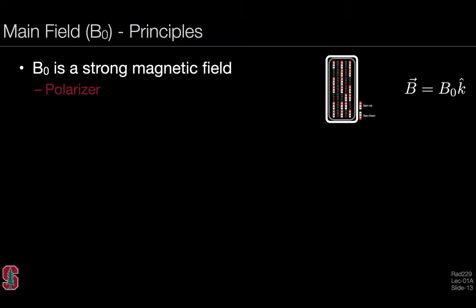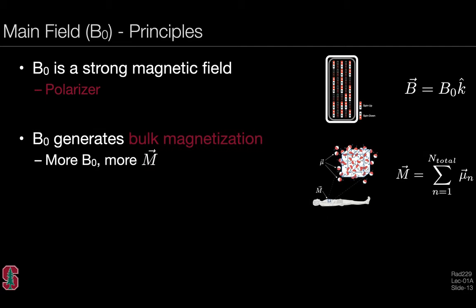Let's think about some principles of the main B0 field. B0 is a strong magnetic field that importantly serves to polarize the spin system or the hydrogen nuclei being used in the imaging experiment. There's the concept of the spins pointing up or down in low and high energy states that gives rise to a net polarization available for detection. B0 generates bulk magnetization—the more B0 we have, the more bulk magnetization we have. This fundamentally underlies the drive to explore higher field systems: 7T systems, 9.4T systems, etc.